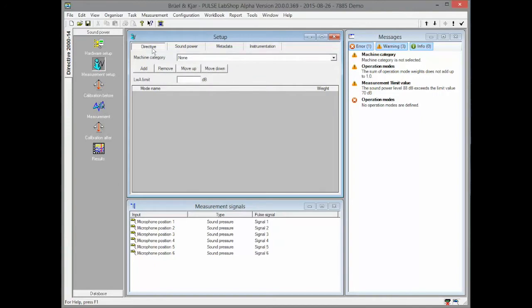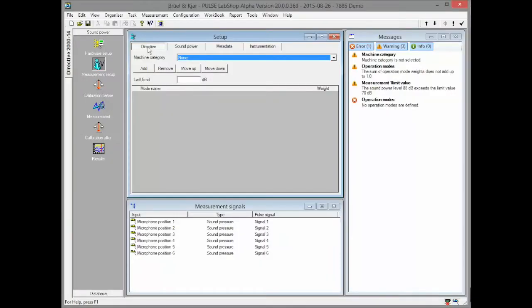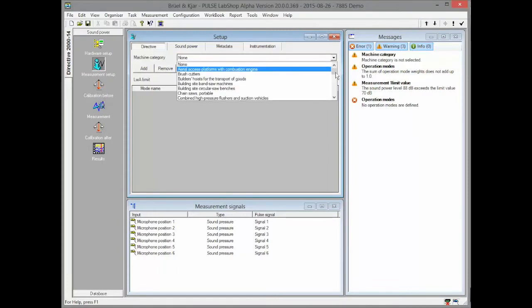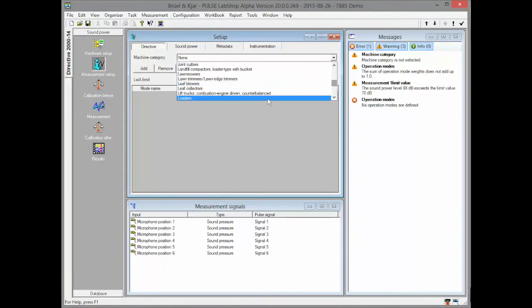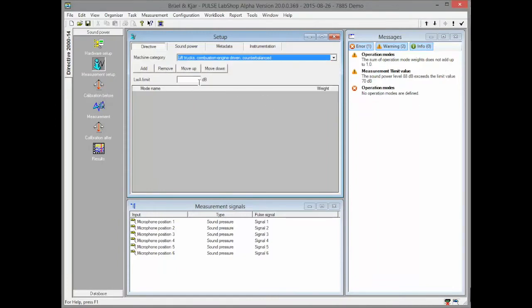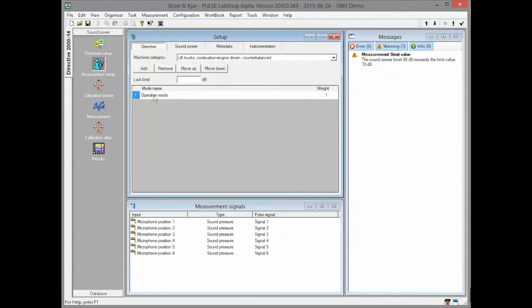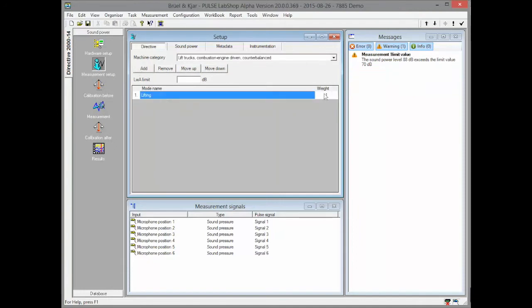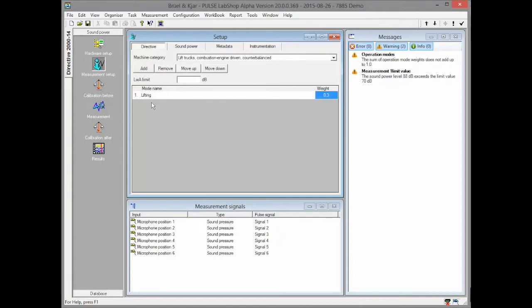Let us return to the first tab and prepare everything for the measurement. When an operation mode is added, its name and weight can be set. The order of the operation modes can be changed. The type of the machine under test and limit value for the sound power can be set as well.